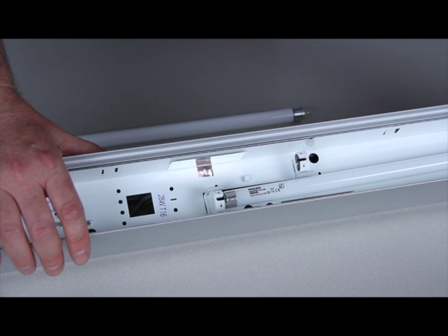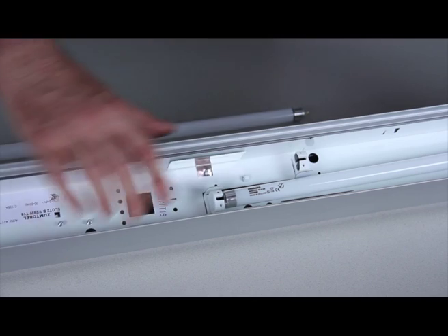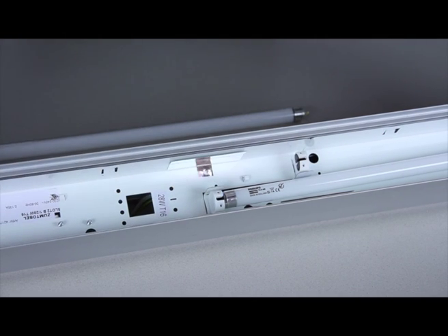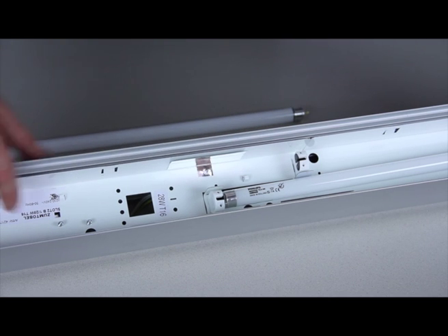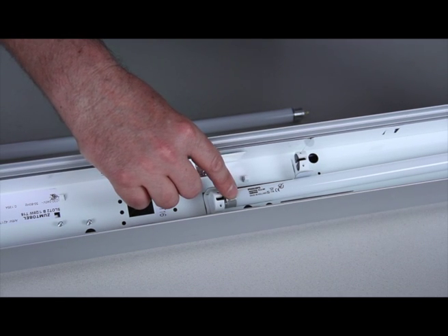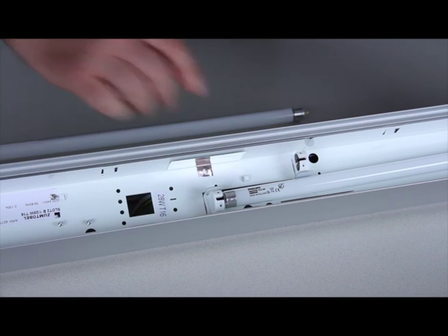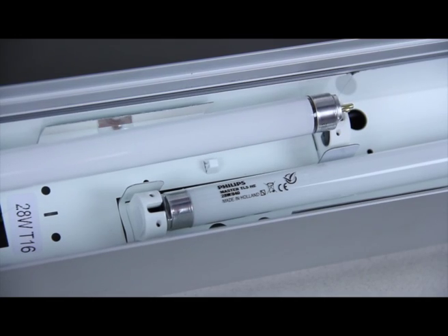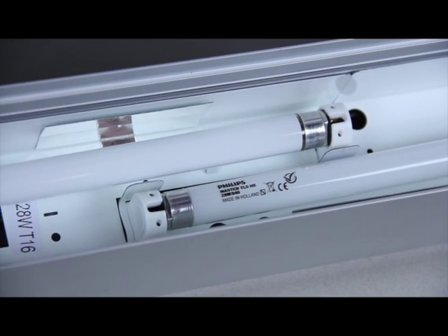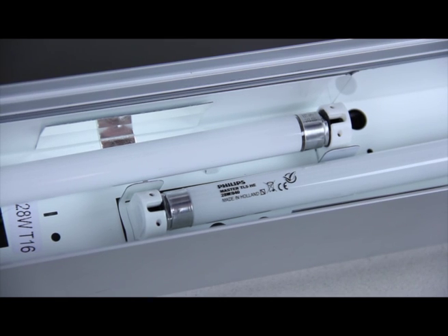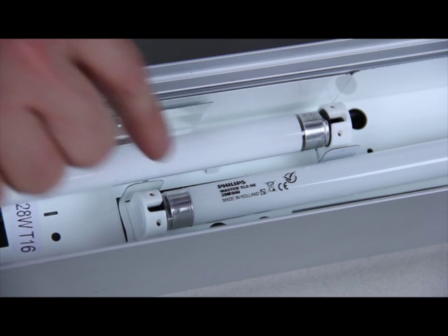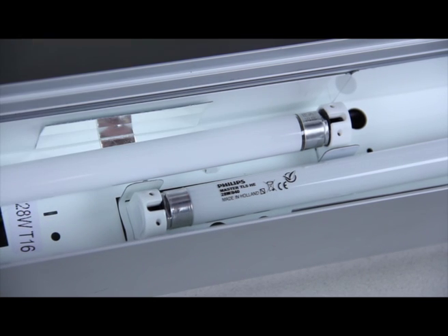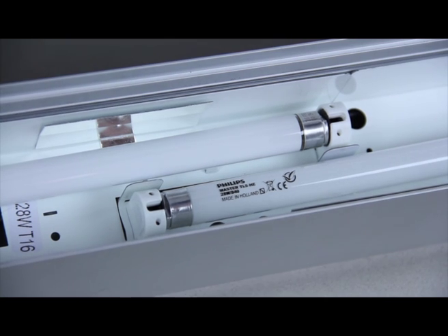To make sure the slot light is evenly lit along its entire length, it's important to make sure that the fluorescent tubes overlap in the correct orientation. Here we see the recommended Philips lamp with the label, and the next lamp on the next gear tray must be fitted with the label at the opposite end. Don't put labels together and don't put non-labeled ends together. Please refer to the installation instructions for more detail.